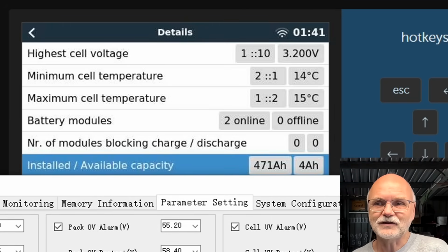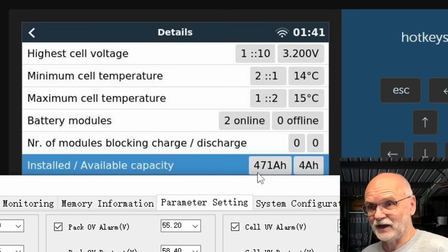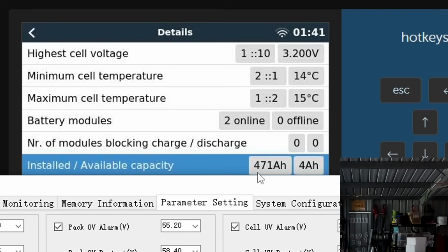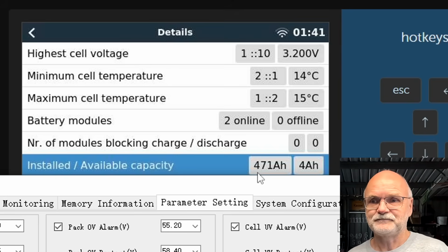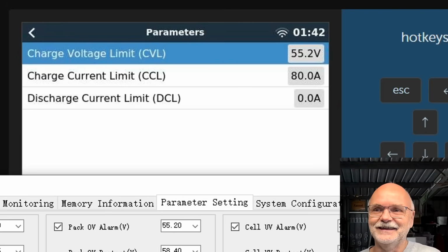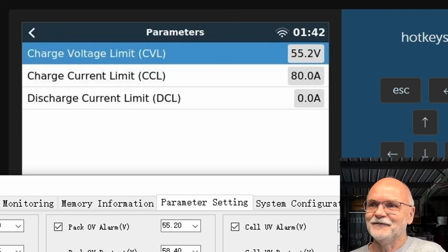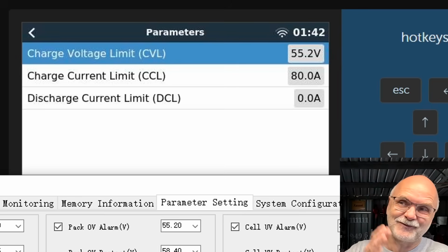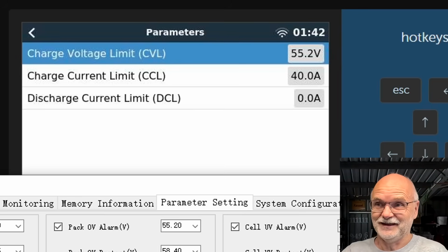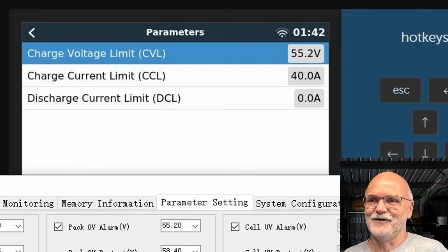See, I'm doing a read only, and it changes the parameters. Okay, turn off the slave again. Slave is unplugged. Yes, it changed to 80. I'm telling the inverter to charge with 50 amps and it should actually take 10 amps off, so 40 amps. Now it shows 40. Why was it 80 before?